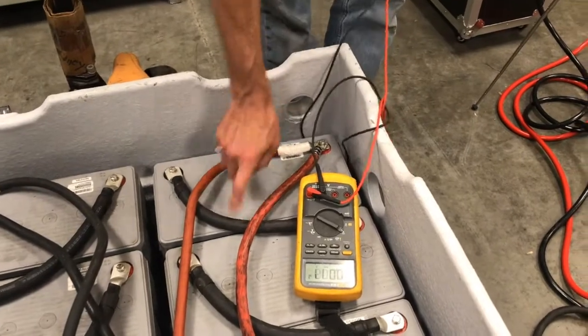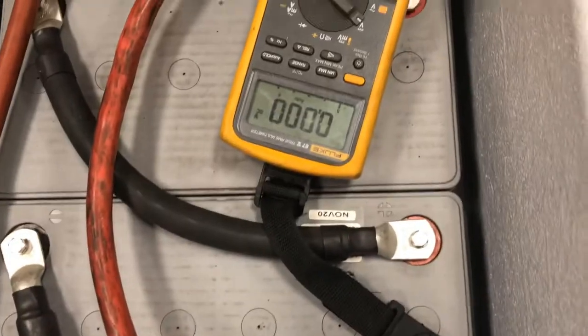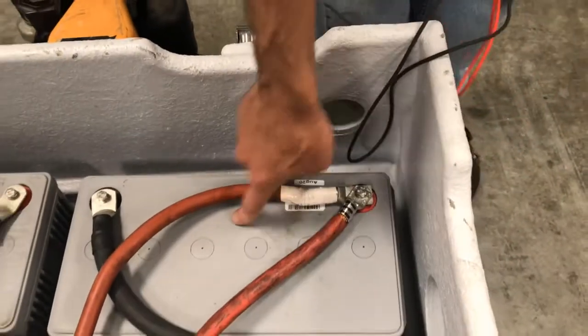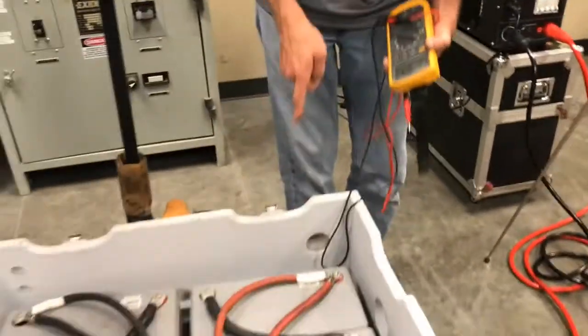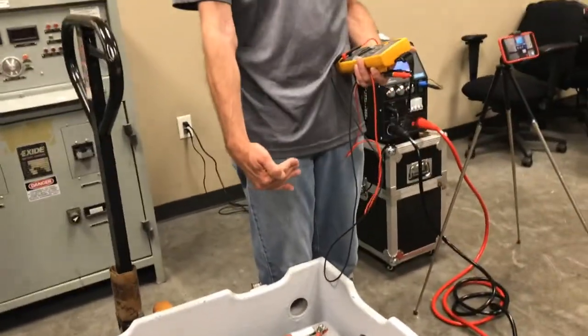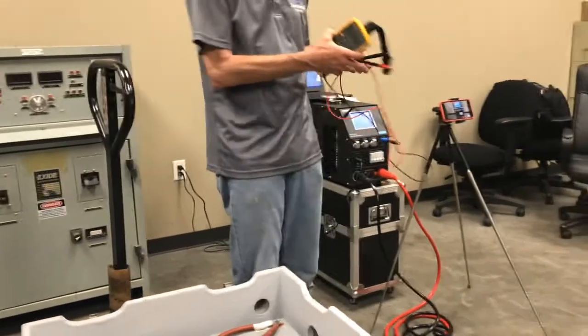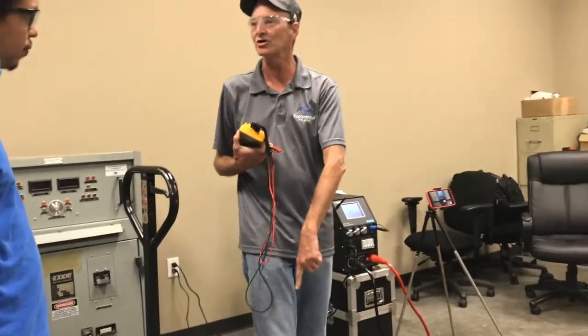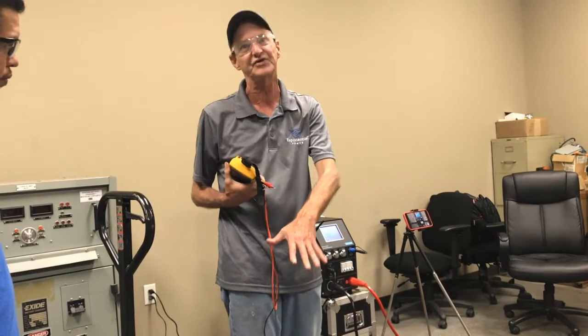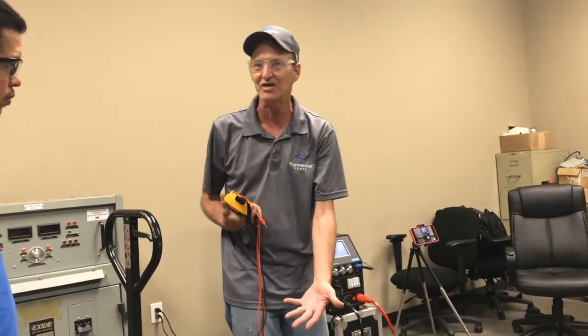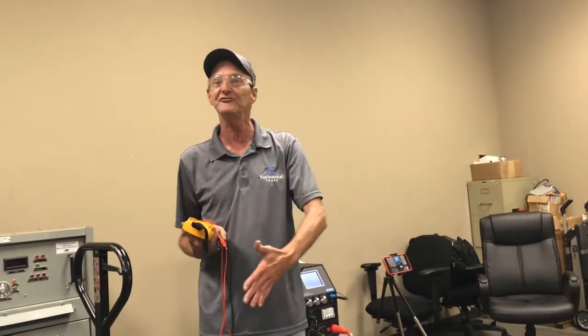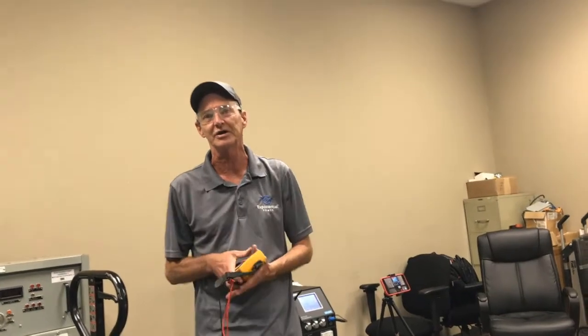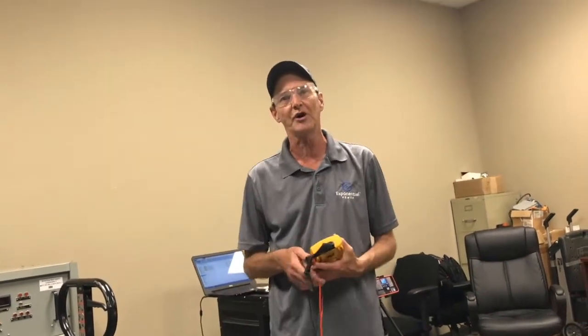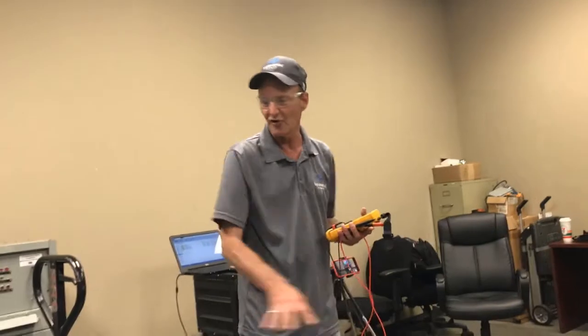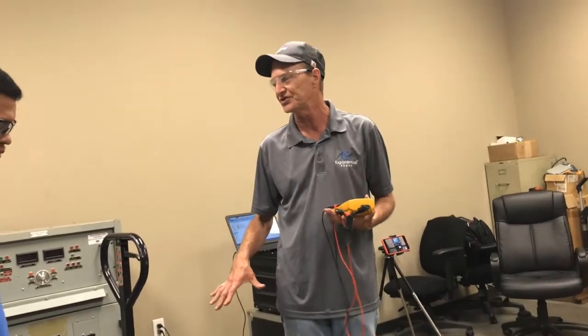Immediately looking at the battery, I can see, oh, different date code. This battery's been replaced. It's not the same age as the others. That would explain why that voltage is slightly higher. On my machine, I may see this battery run a little bit differently than the others because it's not the same age, it's not the same date code, it may have been in a different system, it may be a replacement battery. But by checking overall voltage against the individual voltages, this gives me a starting point for what I should keep an eye on while the test is running.